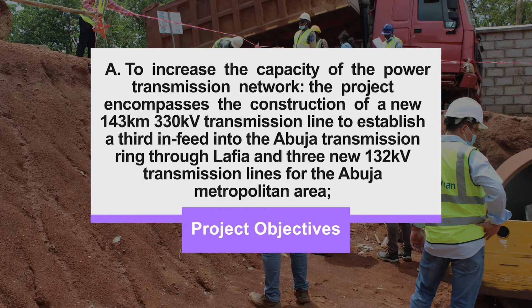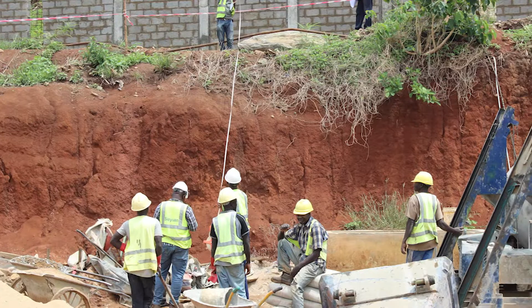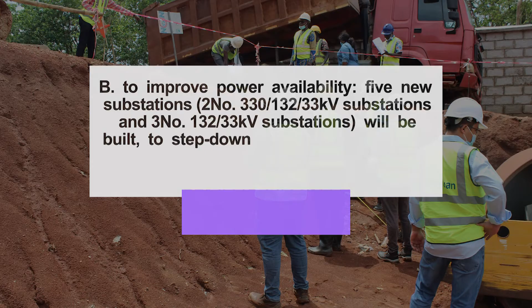The project has a threefold objective. A, to increase capacity of the power transmission network. The project encompasses the construction of a new 143 kilometers, 330 kV transmission lines to establish a third in-feed into the Abuja transmission ring through Lafia, and 3 new 132 kV transmission lines for the Abuja metropolitan area. To improve power availability, 5 new substations will be built to step down incoming high voltage power and supply the local distribution network. C, to ensure stability and reliability of power supply. Now, this includes the provision of telecommunications, equipment, and SCADA integration.